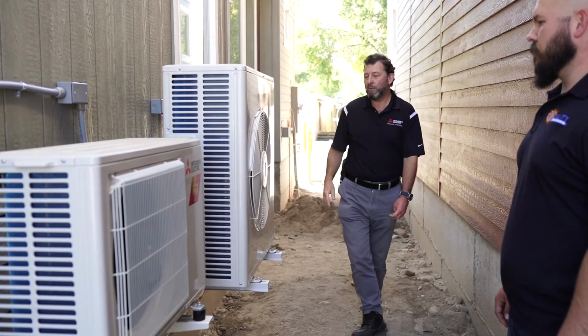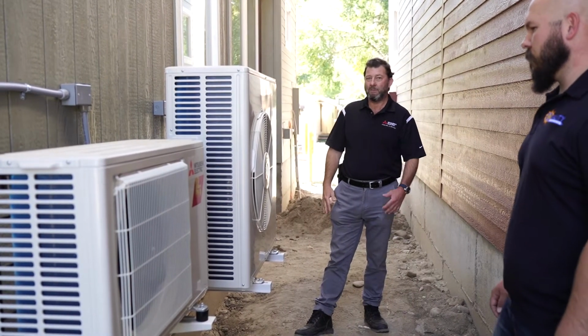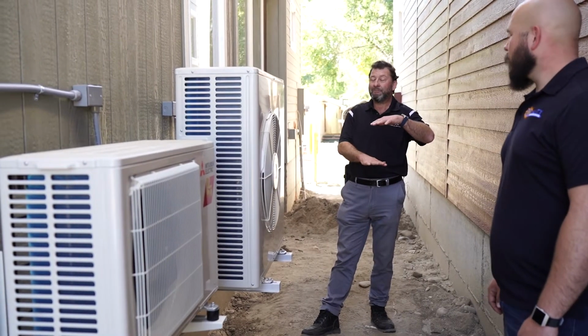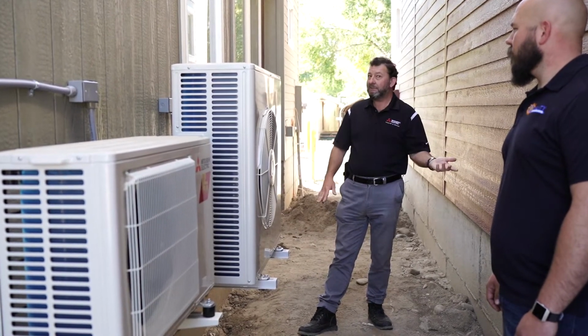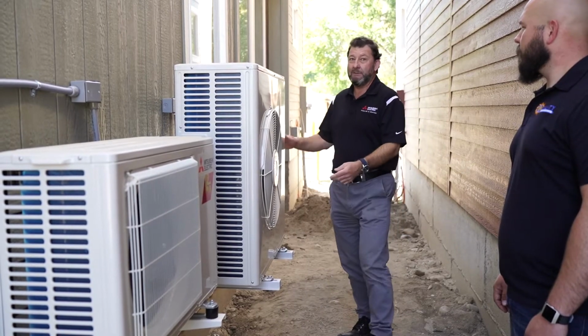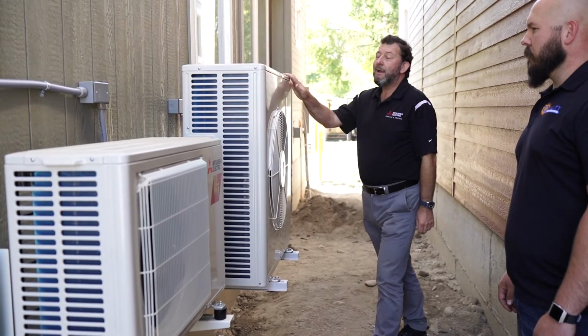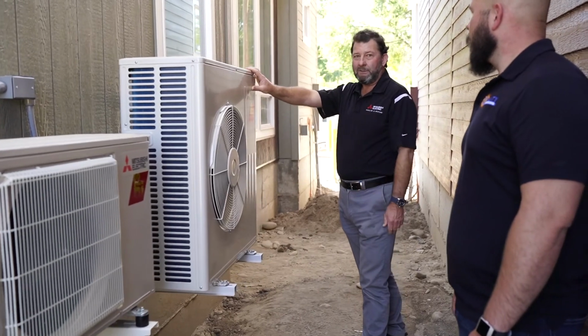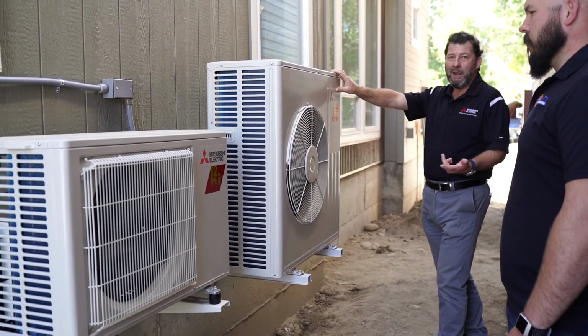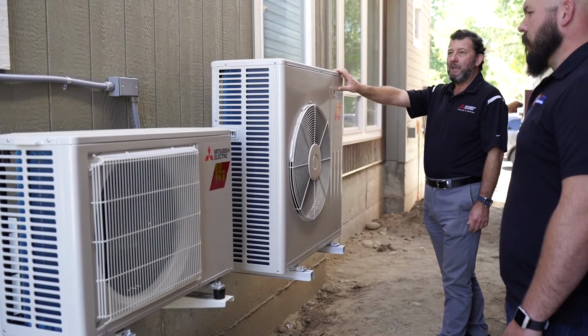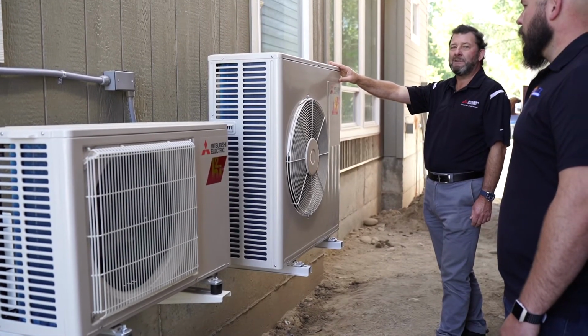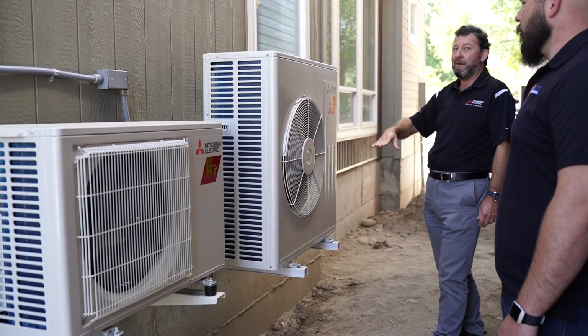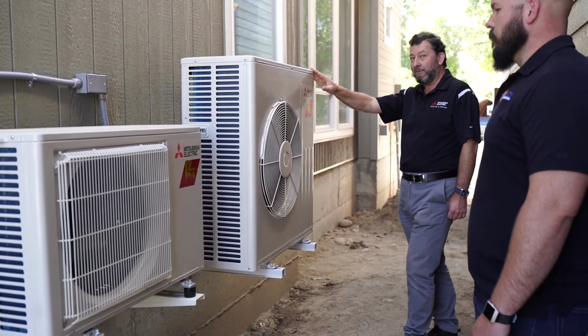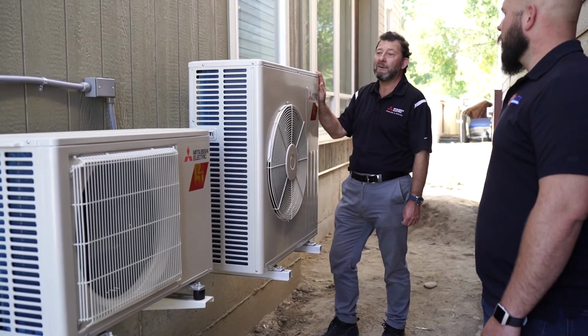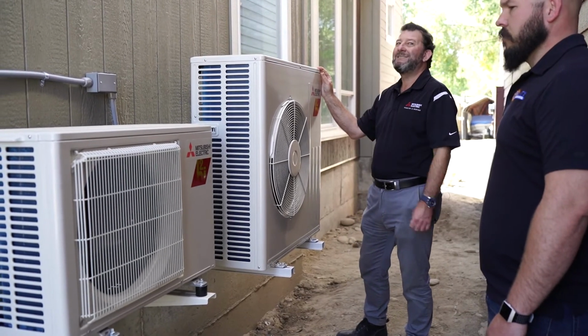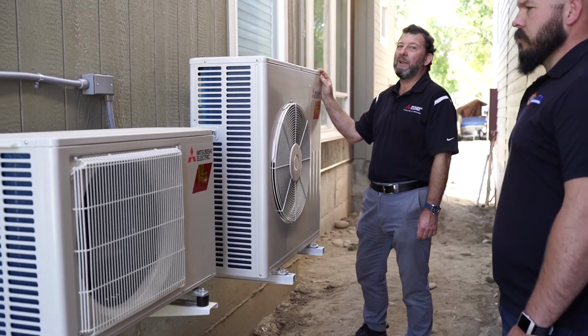One of the issues we're running into in new high performance homes, as heating and cooling loads keep coming down, is that on the coldest day you might need 21,000 BTU, which is what this system is capable of. But in shoulder season, spring, when you need just a little heating or cooling, if you don't have good variable capacity systems, they will short cycle, going on and off. That's not good for the equipment, not good for your energy use, and not good for your comfort. So this is a smarter design, using smaller independent systems for comfort and energy.